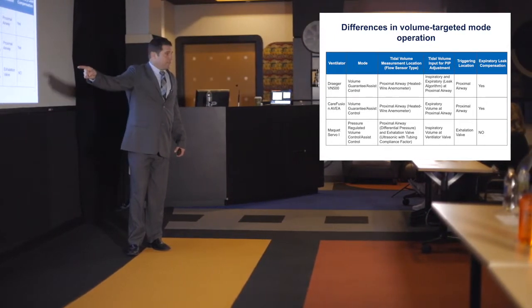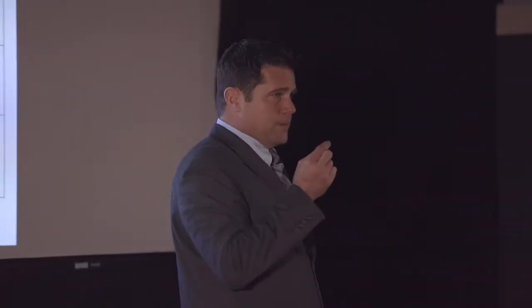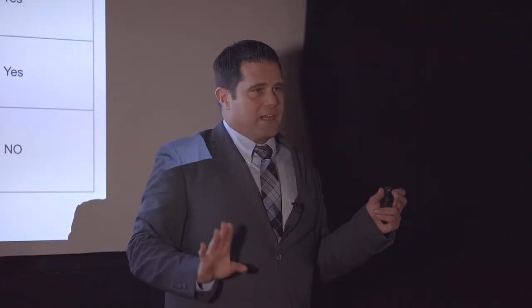But with PRVC, and we tested this in the assist control mode, you can use a proximal flow sensor. It's disposable. But that proximal flow sensor doesn't allow triggering or any input to go back to the ventilator to adjust your cruise control. And furthermore, it uses inspiratory tidal volume that's measured back at the ventilator. So inspiratory tidal volume, what does that mean for a kid that has a leak? Do you think the pressure is going to go down or up? Down, thank you. Because if you have a leak, it's going to see this big inspiratory volume going in to maintain that pressure, because you're adding more flow to maintain pressure throughout the I time. And it's going to say, oh, that volume looks pretty big. I'm going to start weaning the pressures.